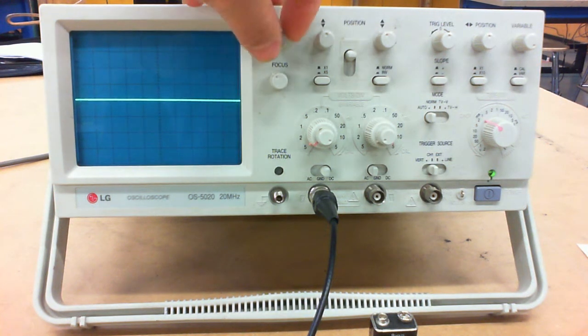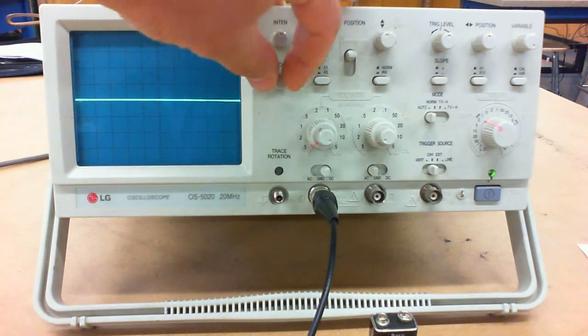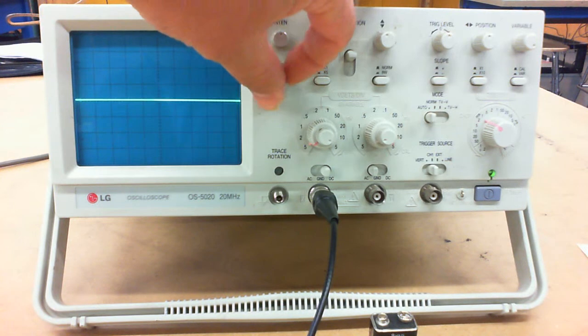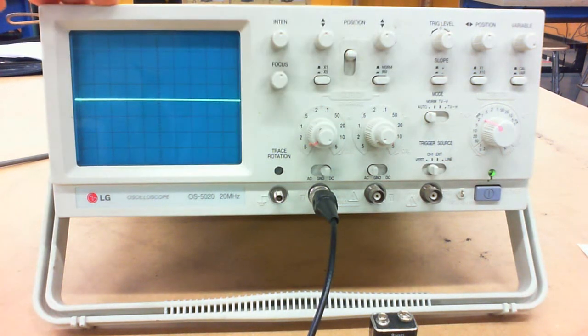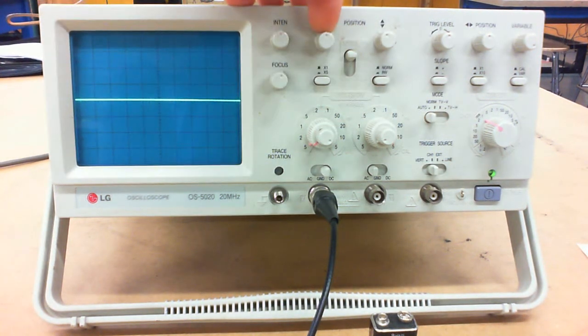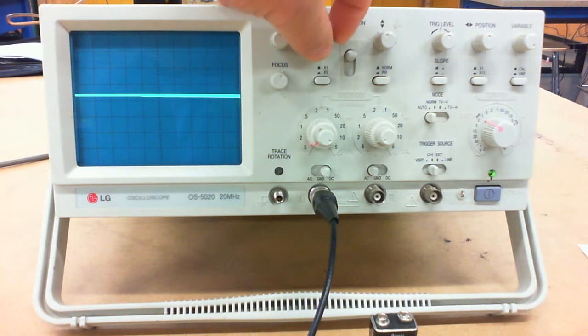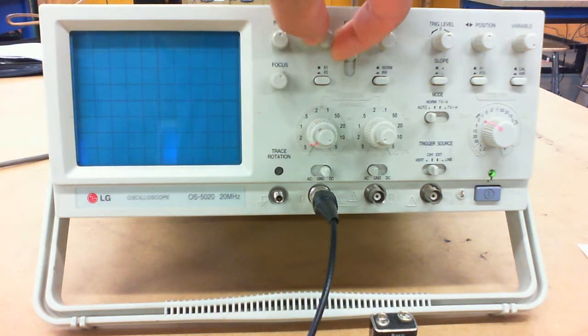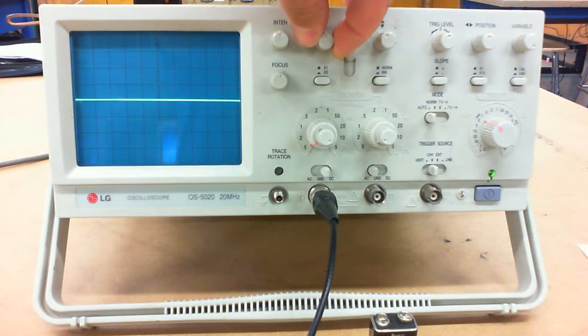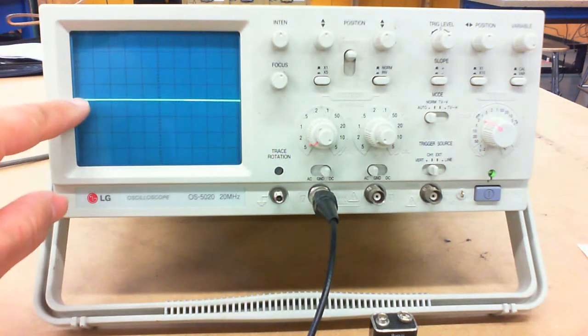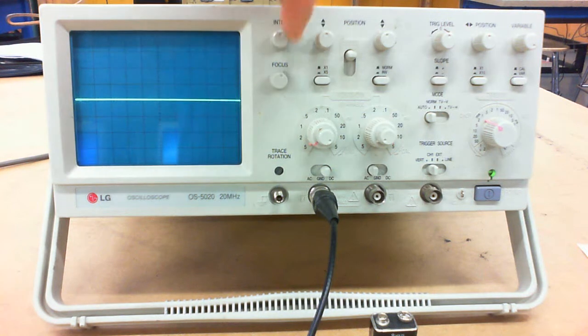The higher the value, or clockwise, the brighter it gets. The next one down is focus, so I can keep it focused. It's hard to see on the screen, but basically I focus it to a nice straight line. I have a vertical position, and sometimes it will disappear off the screen, up or down. So I'm just going to make sure that's set in the center, at the 0 along there. I have magnification. I want to make sure the magnification is not depressed, so it's out, so it's at ×1.